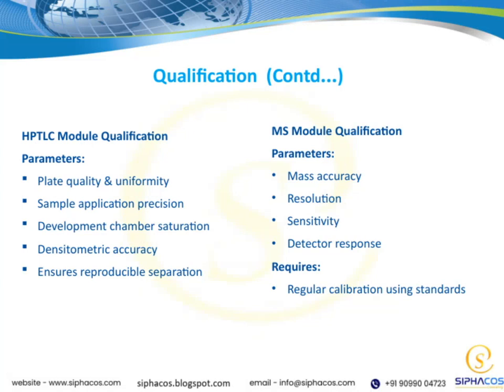Now, let's continue our discussion on qualification, focusing on the MS module qualification parameters. When we're qualifying an MS system, key factors include mass accuracy, resolution, sensitivity, and detector response. These parameters are crucial because they directly impact the reliability and precision of our measurements. Regular calibration using standards is essential here to ensure the system remains accurate over time. Moving on to the HPTLC module qualification, the parameters shift slightly.